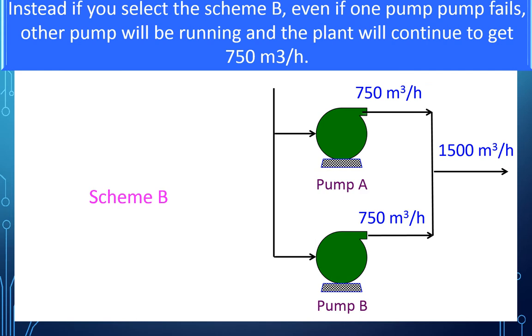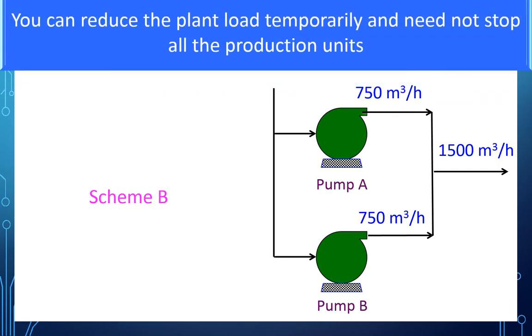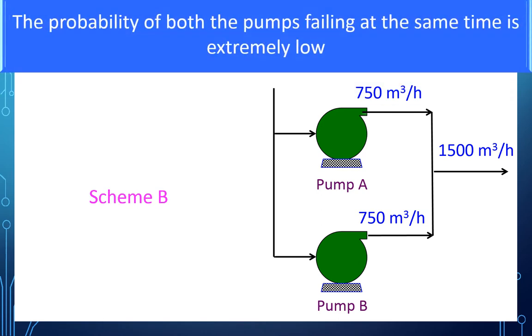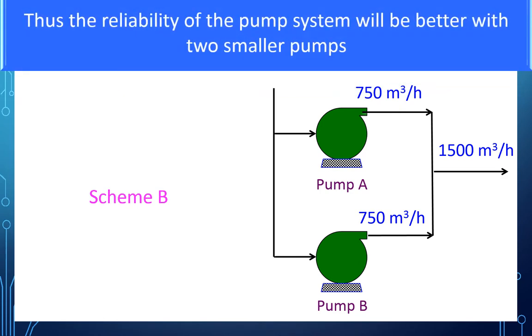And the units will have to be stopped. Instead, if you select scheme B, even if one pump fails, the other one will be running and the plant will continue to get 750 cubic meter per hour. You can reduce the plant load temporarily and need not stop all the production units. The probability of both the pumps failing at the same time is extremely low. Thus, the reliability of the pump system will be better with the two smaller pumps.